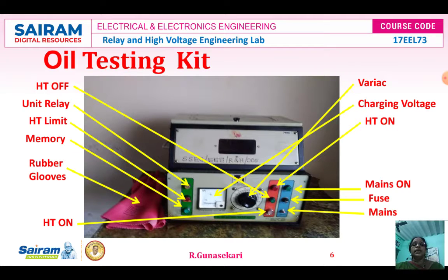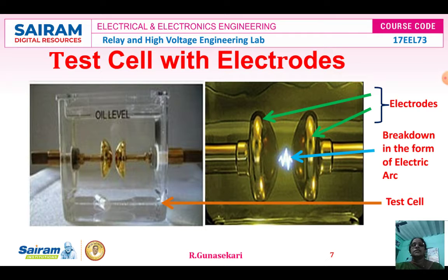This is the oil testing kit image. First column: unit relay indicator, HT limit indicator, memory push button. Next, charging voltage, which is measured in the meter, that is in kV. Then variac or auto transformer. Next, high tension on, that means HT on indicator, HT off indicator, HT on push button. Then mains on indicator, fuse, mains in the form of toggle switch. Then test cell with the electrodes.